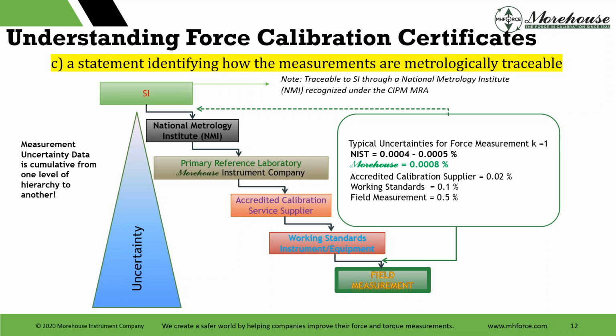The next tier in the pyramid is a primary reference laboratory. That's us. We're here. We're following this. First we start at SI, then we go to an NMI. Here we're at the primary reference laboratory, which is Morehouse, where we have measurement uncertainties at one standard deviation of about 8 parts per million, or 0.0008%.